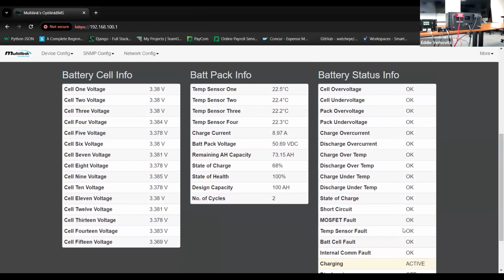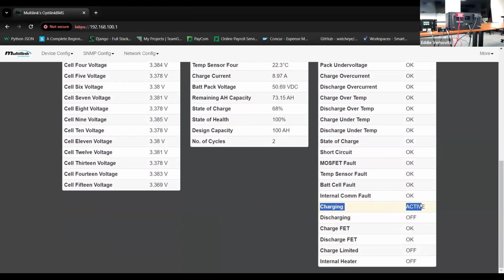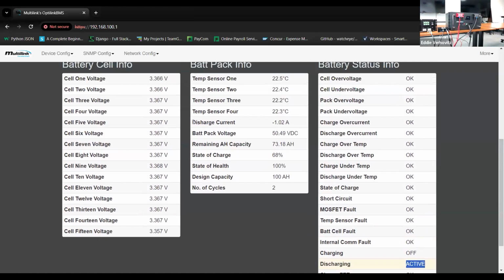During the demonstration, we left the unit in charge mode, so we see that our charging mode is now active. If we perform a brief demonstration, which I'll do off screen, of manually causing an AC power outage, we now see that we are in a state of discharge. The embedded web page automatically changes to show that we're in a state of discharge, indicating the cell using this yellow color as well as this active indicator. Now that we're in a state of discharge, our tables change automatically—before we were charging at 8 amps or so, now we're discharging at 1 amp.